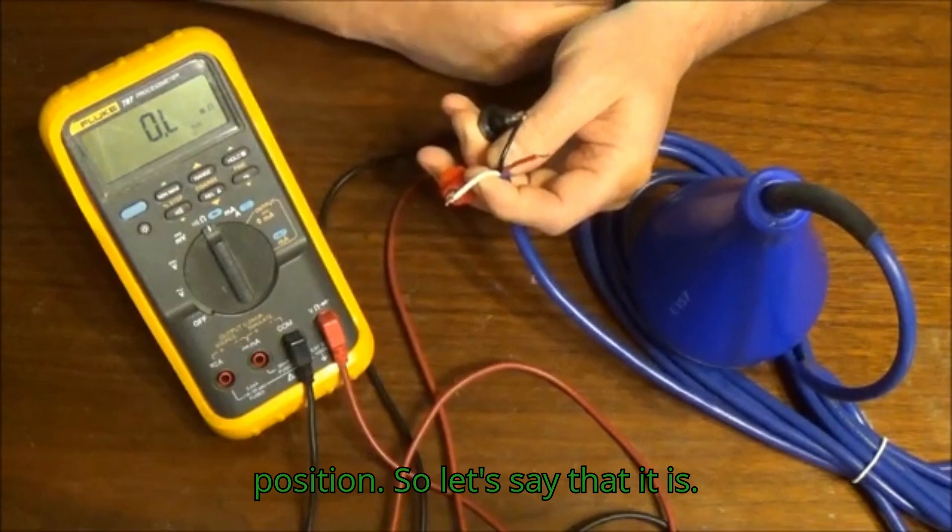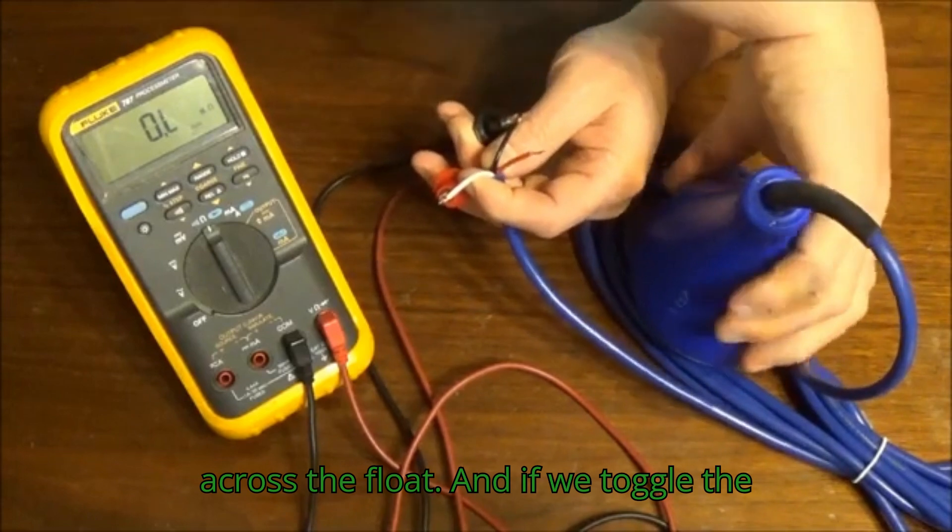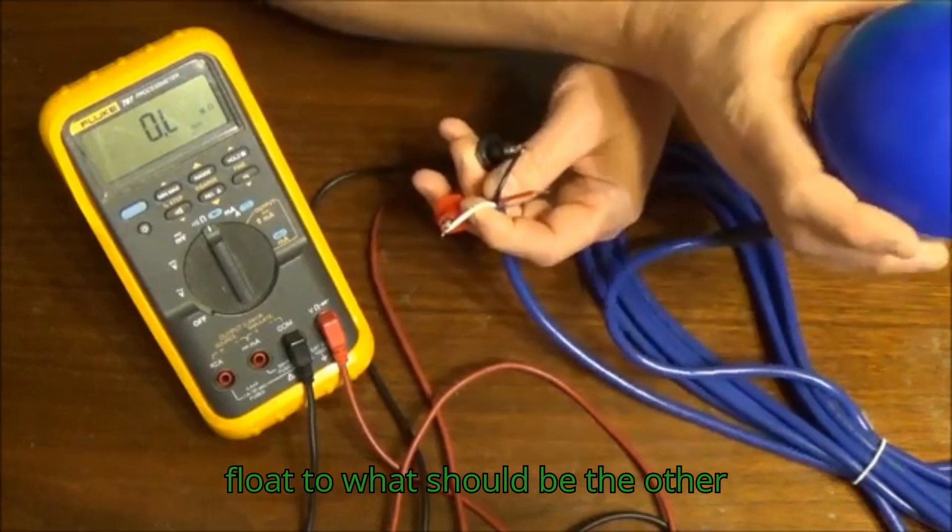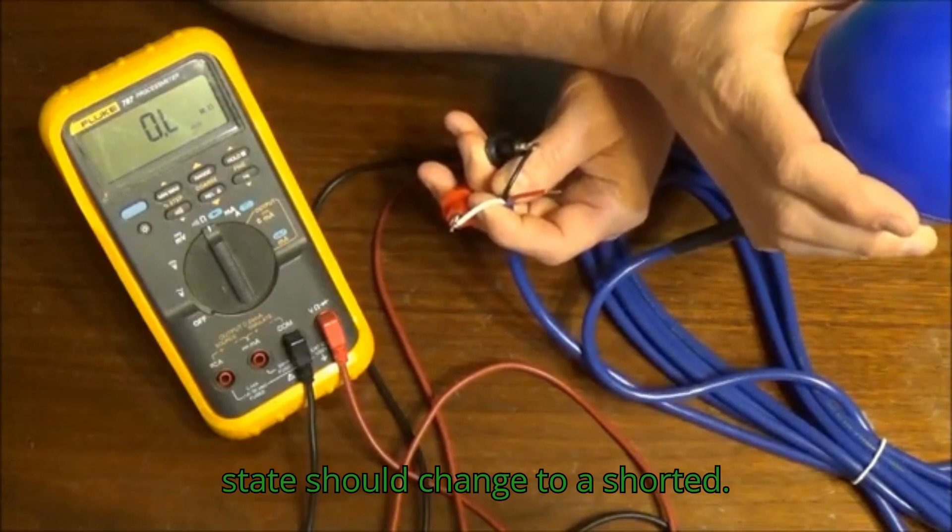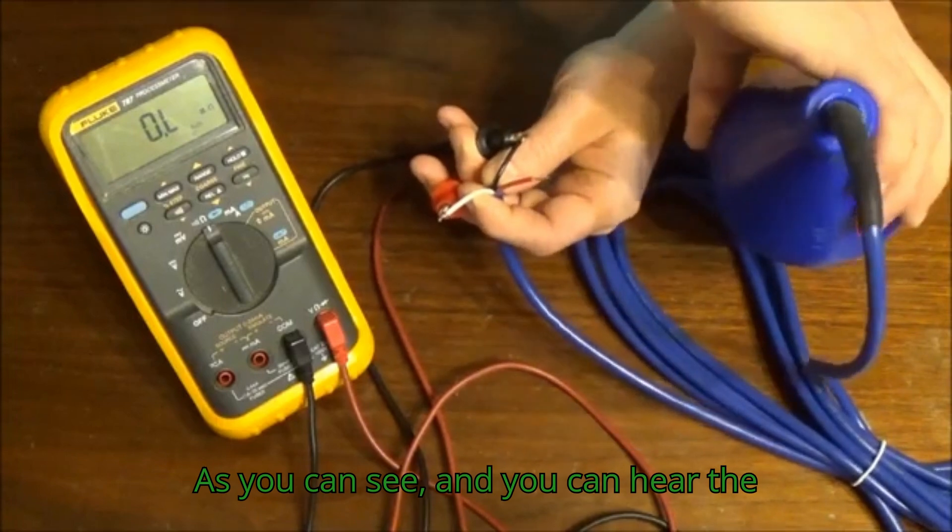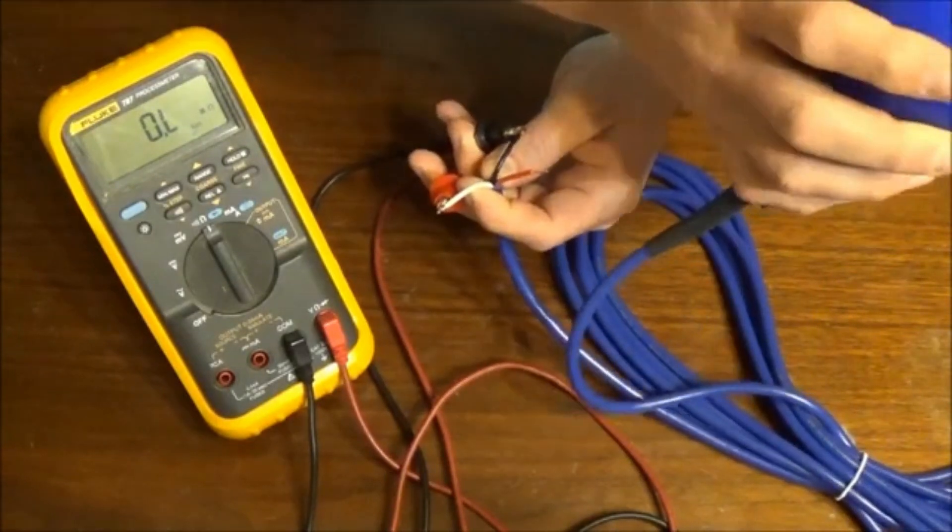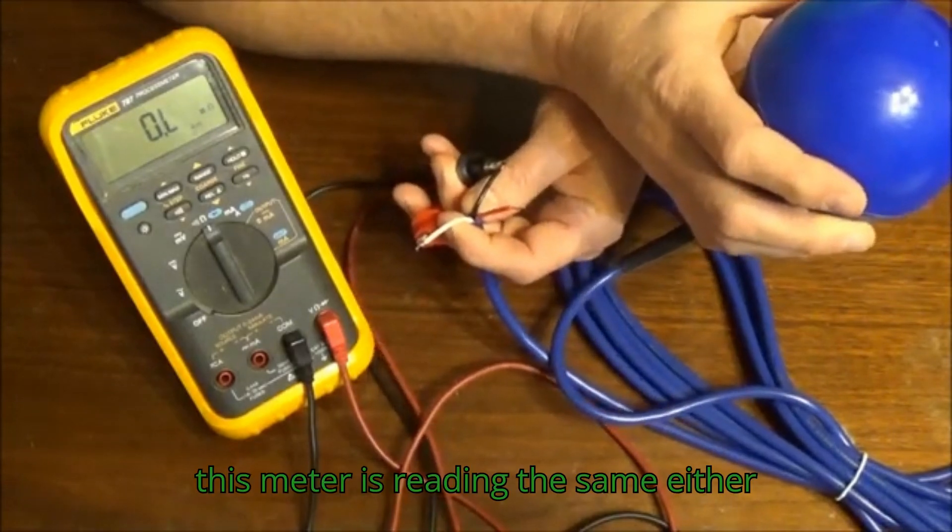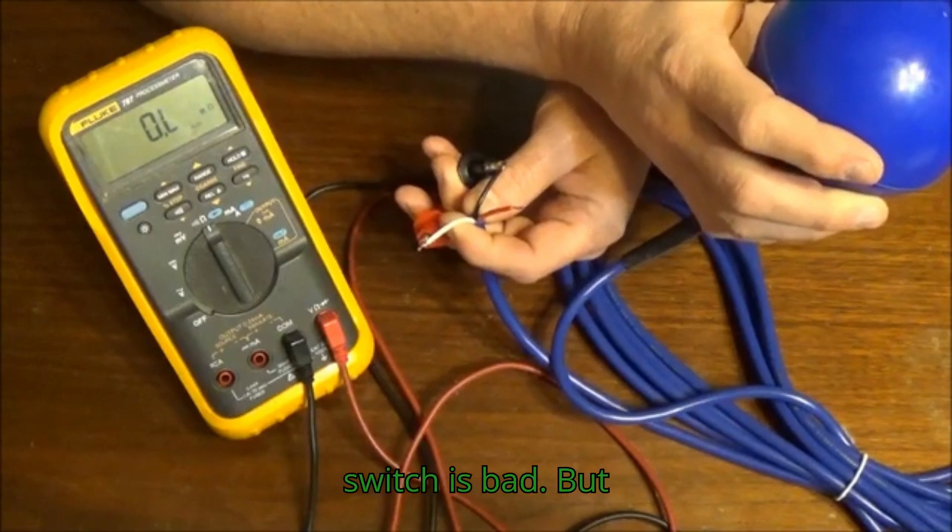Let's say that it is. We've got the leads measured across the float. If we toggle the float to what should be the other condition or opposite condition, that state should change to a shorted. As you can see and hear the switch toggling, this meter is reading the same either way, indicating that the float switch is bad.